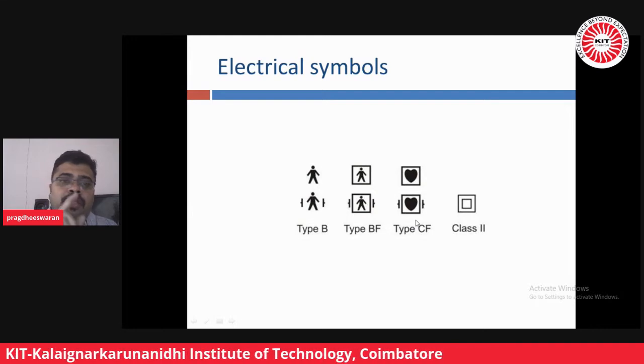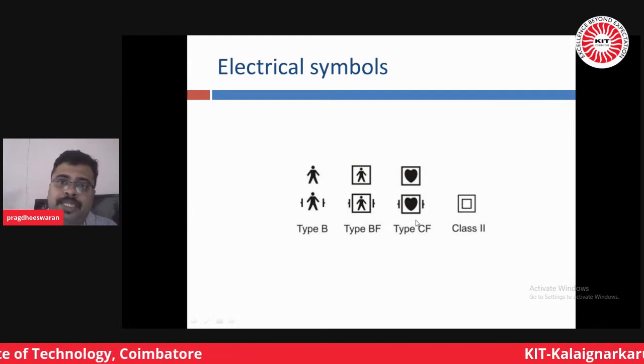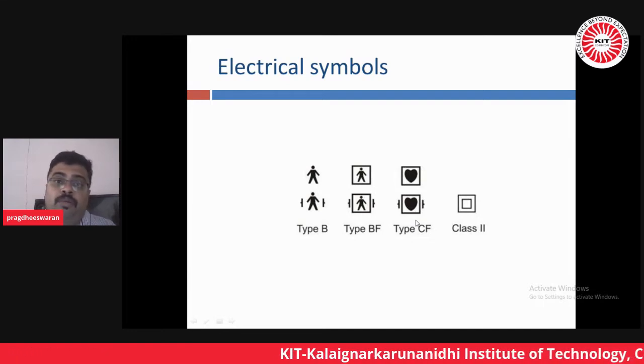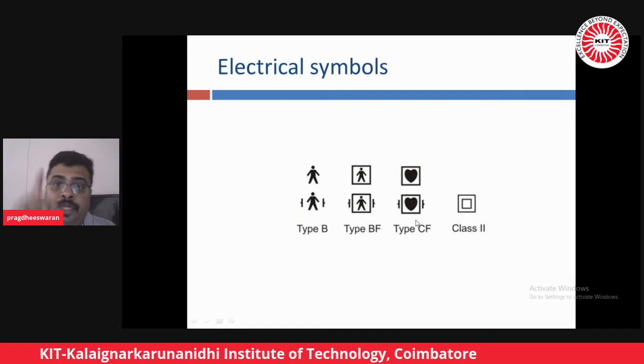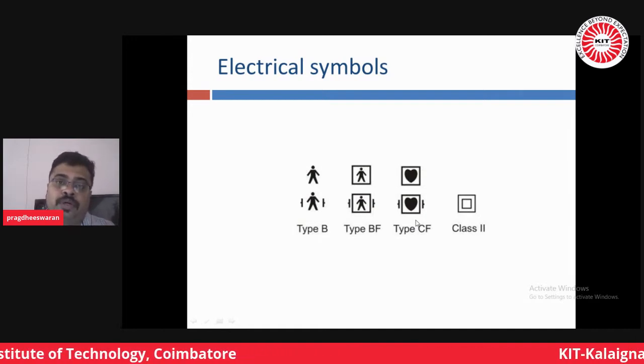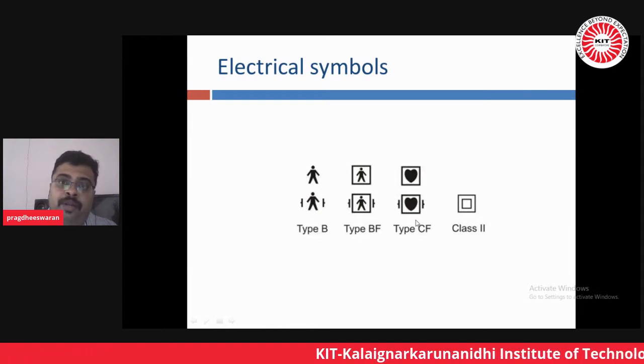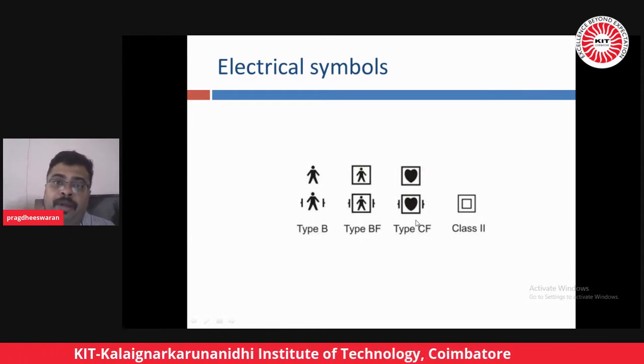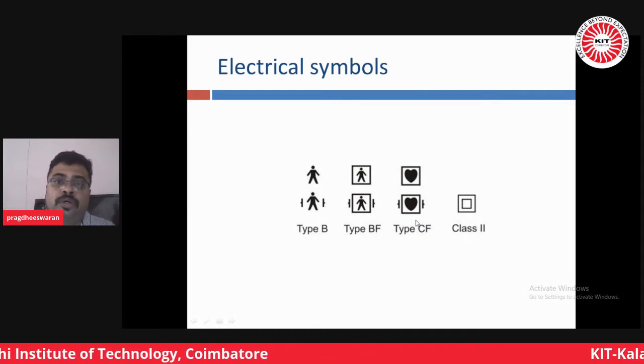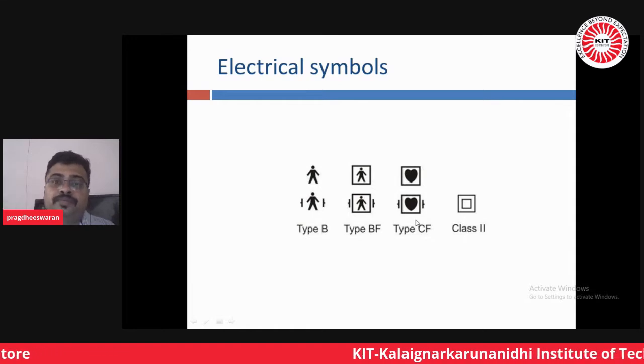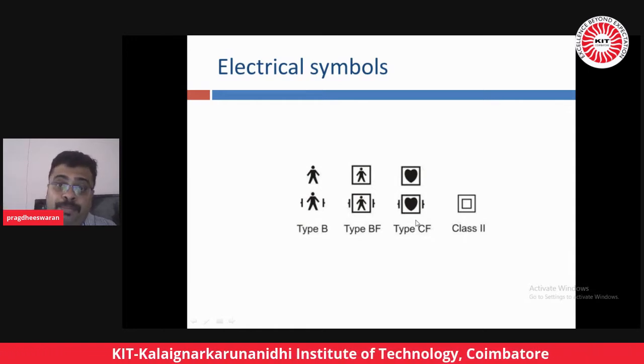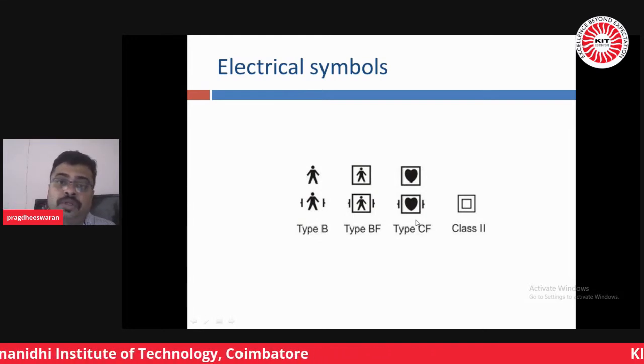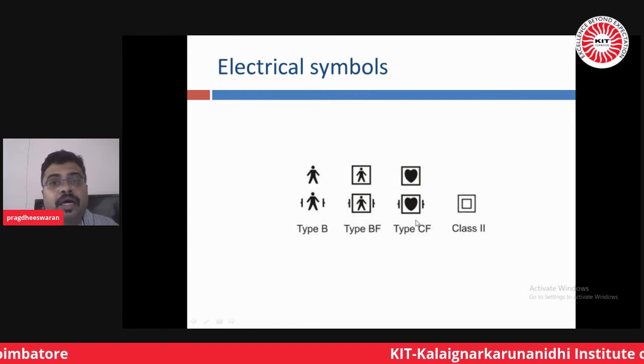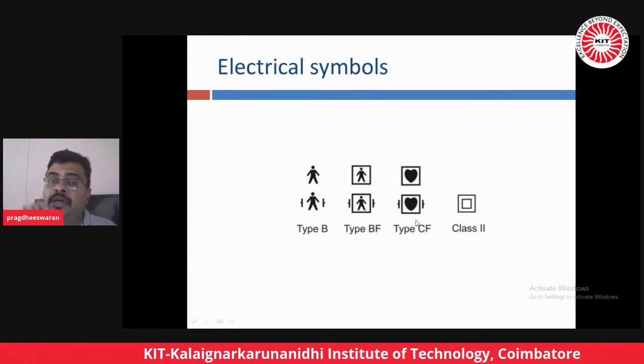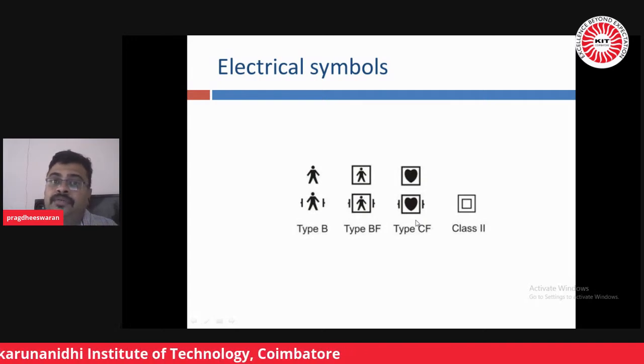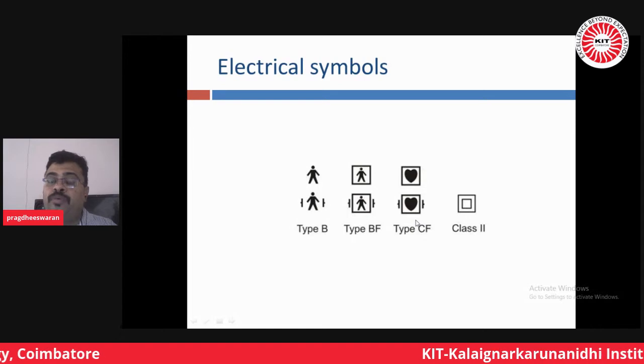Sometimes what will happen is the combination of problems: phase may come on both sides, still your equipment works. Neutral comes on both sides and phase comes on the earth line, still your equipment manages to work. Phase is available, earth is available, neutral is partially available or not available, still your equipment manages to work. Phase and neutral are available, earth is not connected at all. Your equipment is designed properly as per the insulation procedures, but earth is not there, still your equipment works. But it is called a single fault condition. In this single fault condition, the leakage currents will increase. That is where we have to be very careful.